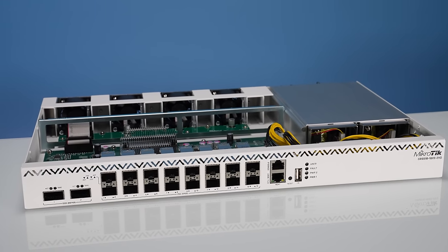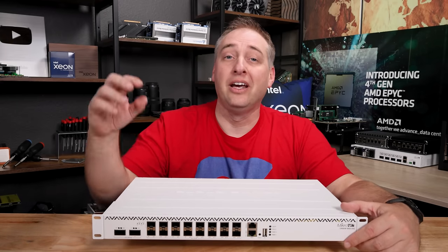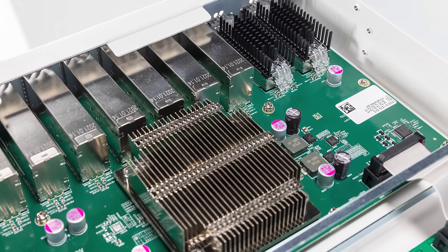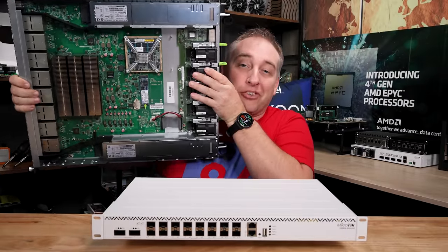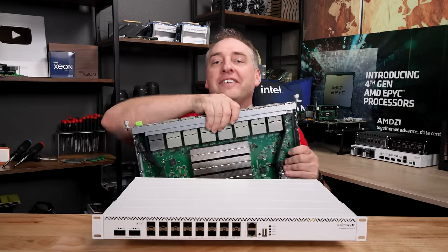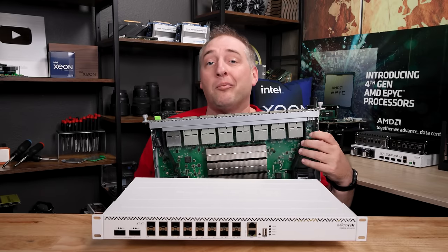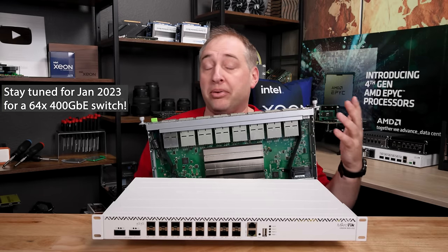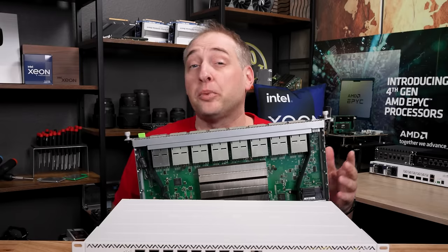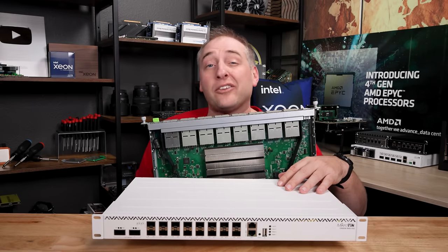Looking inside the switch, there are a couple of interesting design choices to call out. First, the QSFP28 cages have relatively large heat sinks. For comparison, on a Facebook Wedge 100 switch, the QSFP cages don't even have heat sinks — that generation assumed strong data center airflow. On the MikroTik side, they're running larger heat sinks on the QSFP to make sure optics don't overheat, because MikroTik is trying to minimize fan speeds.